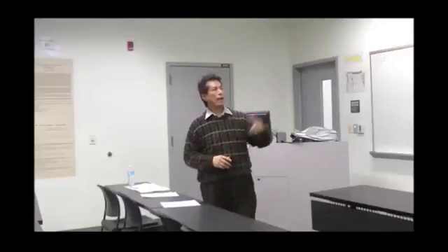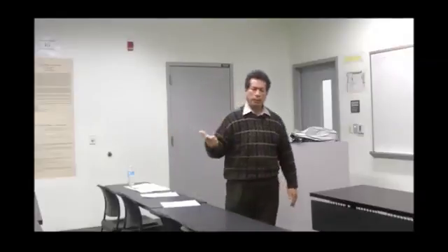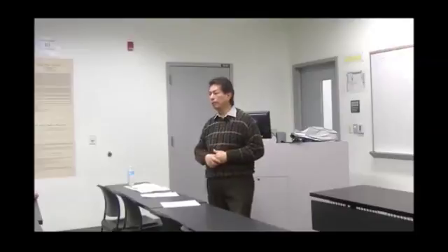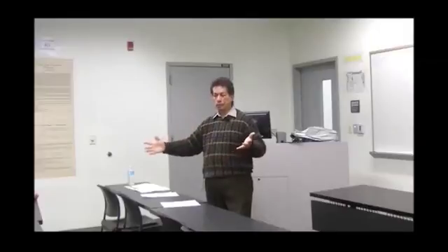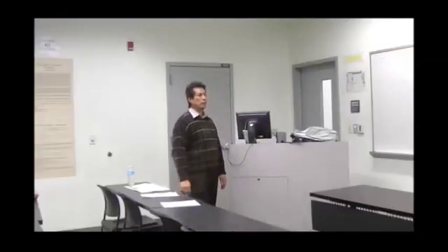Help desk or service calls. How many? What level? Power, plumbing, or HVAC? Which one do you think I get the most calls for at my site, General Dynamics? HVAC. I get more hot and cold calls than anything else, hands down. Very little lighting calls. A tripped breaker, very seldom. And if it is a tripped breaker, you do the diagnostic, what caused it to trip. So you put a meter on that particular unit and you record the load and pinpoint what was the root cause. Plumbing is either or, right? So absolutely, HVAC calls would be the biggest.